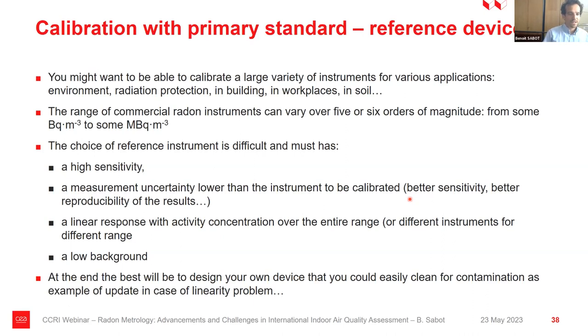So all this combined, it's not so easy to find a reference device. So I would say that at the end, it's always best to design your own reference device, because you will know how it works. For radon, it's not so difficult. Let's say that it's always difficult, especially if you want to reach a low background, because you always have this problem of polonium-210 when you reach high sensitivity of detection for radon. Anyway, this is one of the parts when you want to calibrate a reference device.